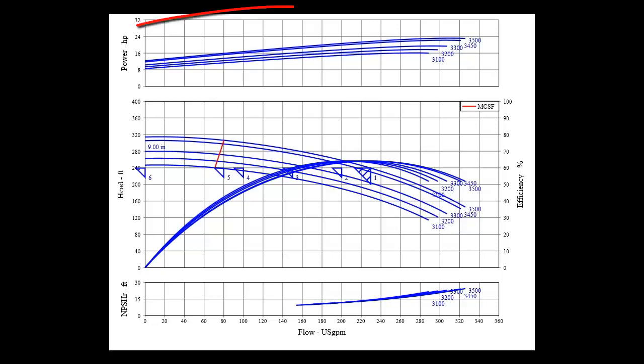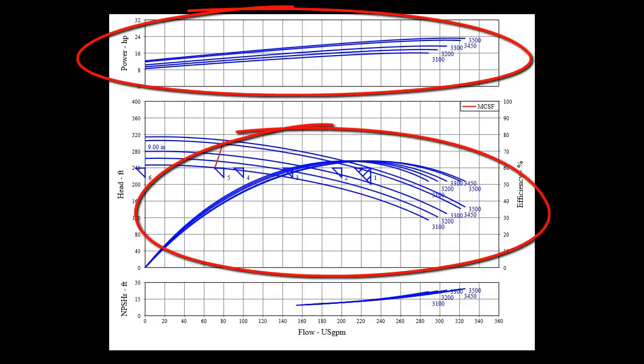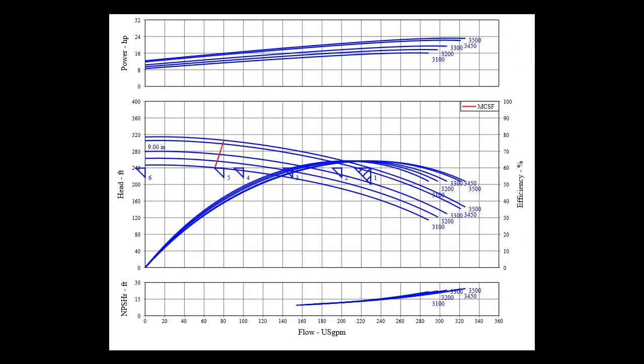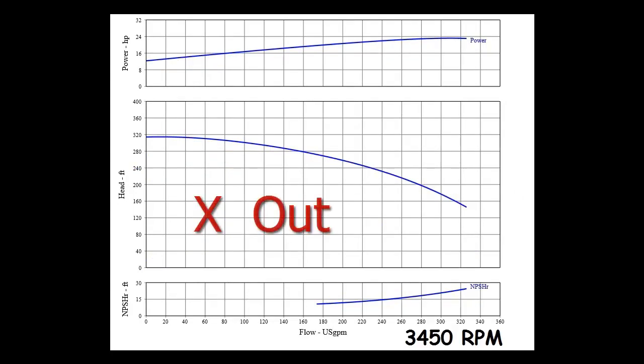Pump curves can show the horsepower, the efficiency, and the net positive suction head required. It can also have multiple performance curves depicting different impeller diameters and or multiple pump speeds. Don't let any of this confuse you. Most pump companies electronic catalog will let you X out the parts you don't need to see. In most cases we only need to look at the performance and horsepower curve for a single speed pump with a set impeller diameter.